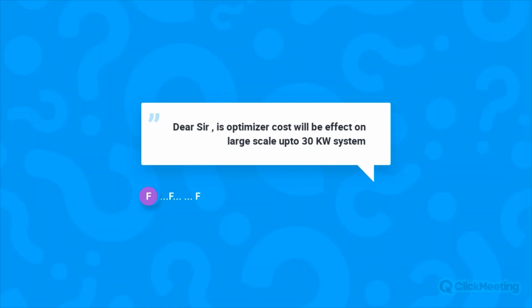But the benefits that you get from the optimizers, in terms of improving the optimized power produced from PV panels that are mismatched in this situation, or if you're using it in a longer string design to maximize your PV production, you must take a look at the trade-off of that with the cost of the optimizers. If it absolutely makes sense for you, then it will make sense for the whole system. So I think that's what you take a look at. But ideally, we are aware that the optimizers are not too expensive, and considering how they're able to ramp up the power for you properly, I think it will be worthwhile for you to adopt it.